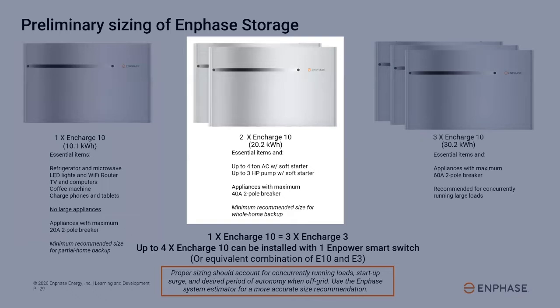For whole home backup scenarios, at least 2 Encharge 10 units is recommended. This system can start and run up to 4-ton air conditioners and 3 horsepower pumps, provided soft starters are installed. Most appliances wired to a 40 amp 2-pole breaker can operate with 2 Encharge 10s.